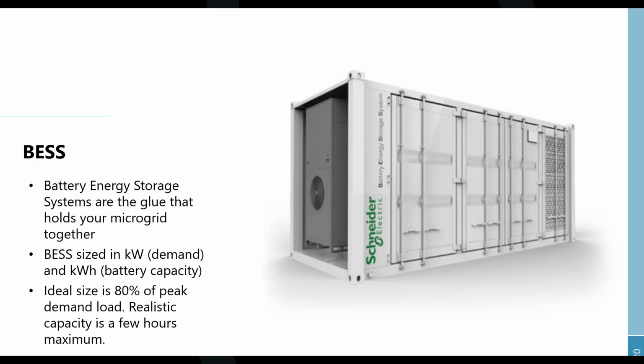Where are they located? These things are located outdoors. You really want to locate your battery energy storage system in almost all cases outdoors due to the fire risks associated with them. And just a general rule, you want it to be sized to 80% of your peak demand load. And unfortunately, the realistic capacity is just a few hours. So typically, you'll have about 2 hours standard for a battery energy storage system, which is why those generators form the backbone to give you extended runtime. But these are there when you need power quick.